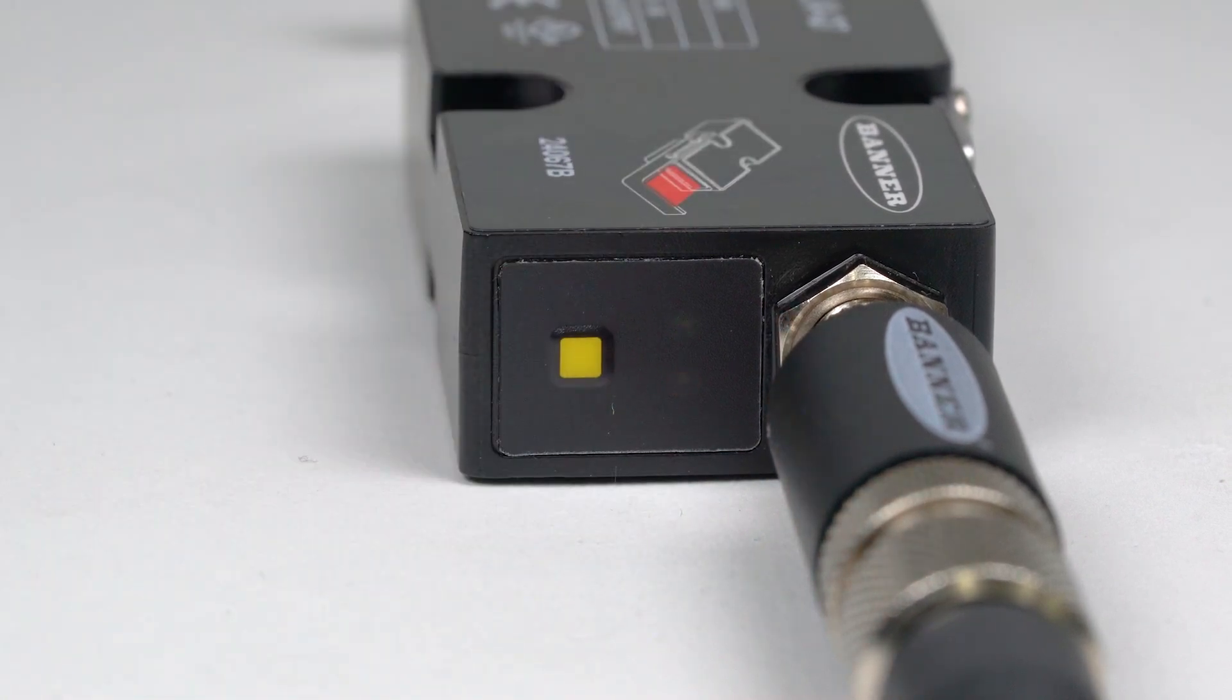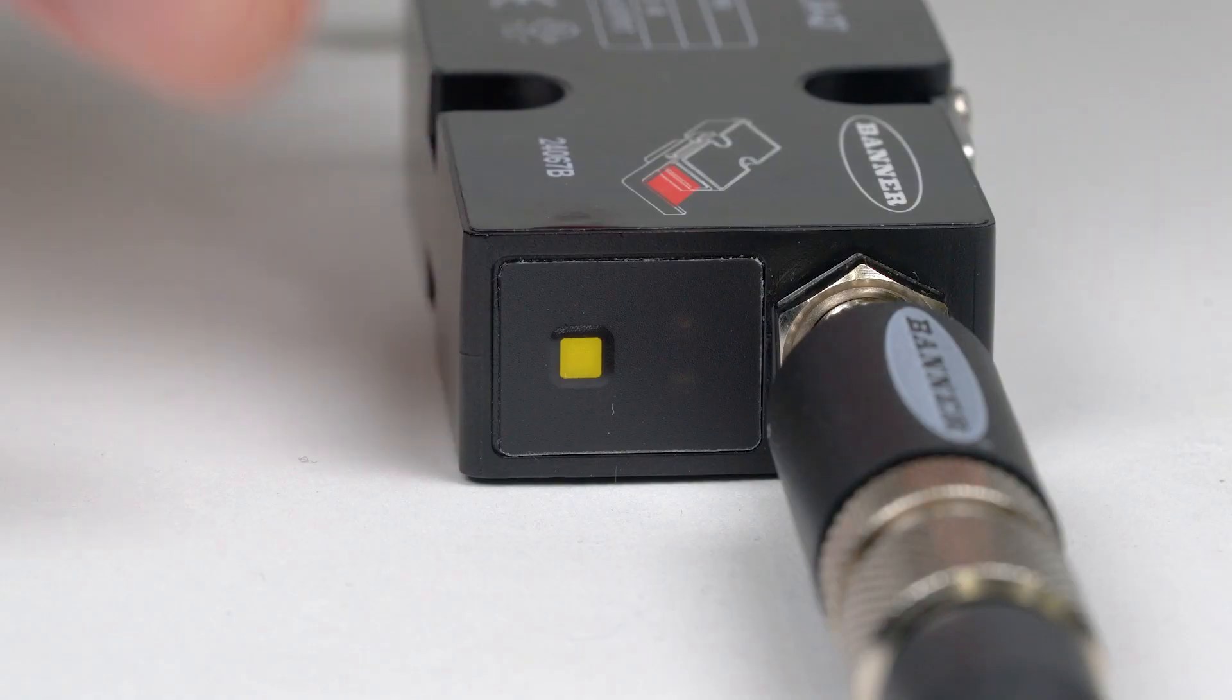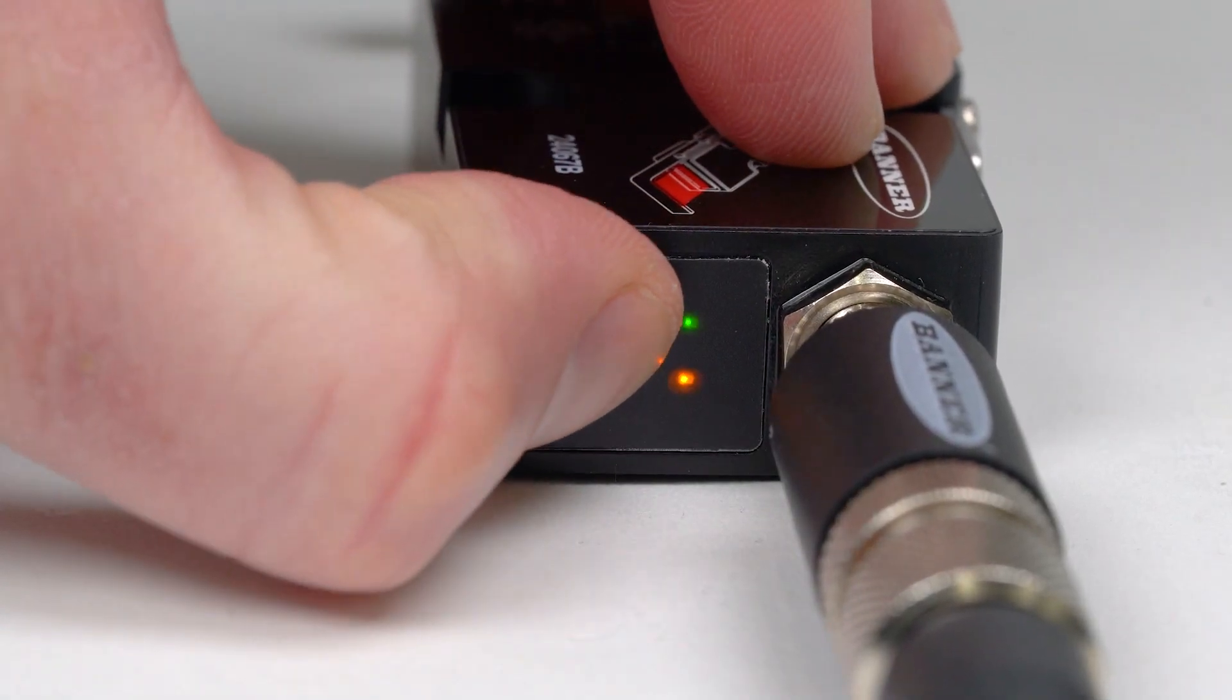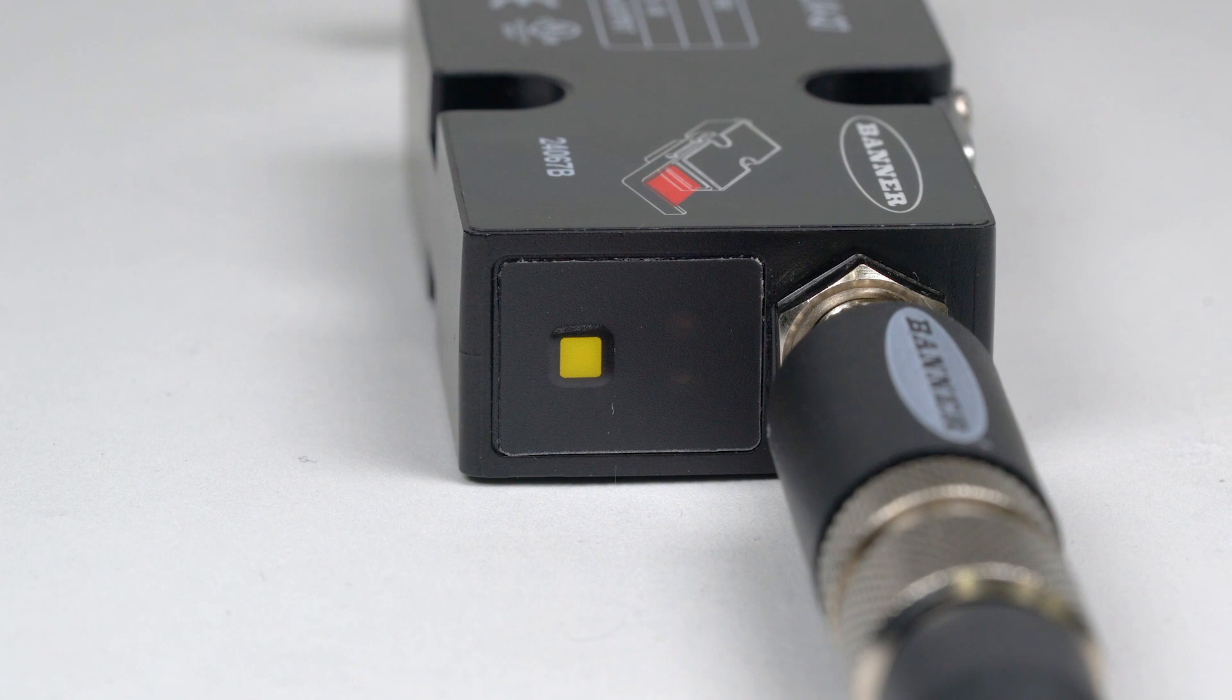The LEDs will start double flashing to indicate that it is ready for the second teach point. With the beam still clear, press the button one more time. The green LED will flash twice to confirm that the single edge detection range has been set and the sensor will return to run mode.